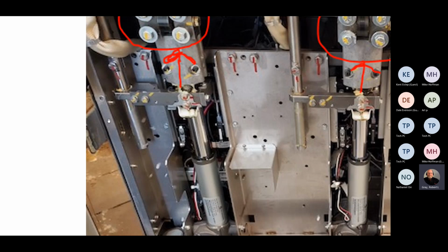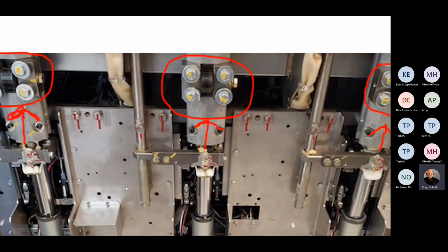So make sure you use the appropriate fastening screws. All right, don't use the wrong ones. Right here is that roller mechanism that I showed you, the flat portion of the upper shaft. That roller helps with the sway, from left to right of the arm. There's a question on the test with the arm moving left to right. It says platen/arm, capitalized, moving left to right. It's referencing the arm movement. That's going to be your bolt on top, the 9/16 inch bolt on the knuckle, and your cross member assembly right here. Something could be loose.